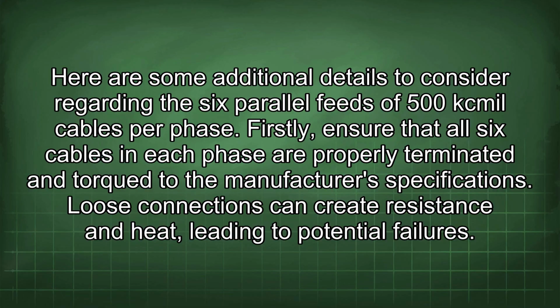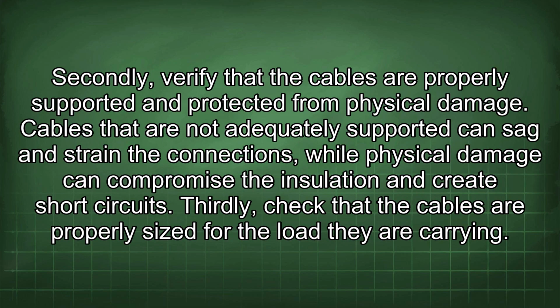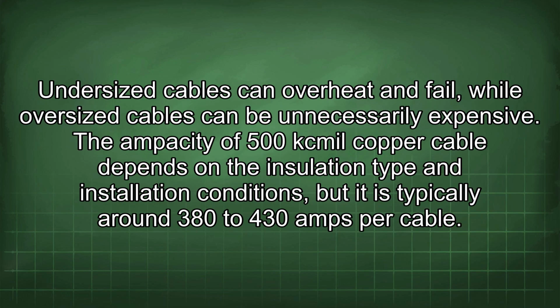Firstly, ensure that all 6 cables in each phase are properly terminated and torqued to the manufacturer's specifications. Loose connections can create resistance and heat, leading to potential failures. Secondly, verify that the cables are properly supported and protected from physical damage. Cables that are not adequately supported can sag and strain the connections, while physical damage can compromise the insulation and create short circuits. Thirdly, check that the cables are properly sized for the load they are carrying. Undersized cables can overheat and fail, while oversized cables can be unnecessarily expensive.